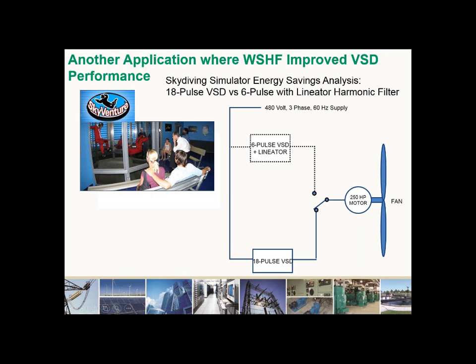These skydiving simulators are basically large fan systems blowing air out, and you step in and you can float on the air. You can see this is somebody sitting in a skydiving position. You can do various tricks and so on. A lot of fun to participate in. When they run these, they run them at varying speeds, but the two speeds they typically use are full speed, when the instructors or a very skilled skydiver is using the equipment, at 889 RPM fan speed, and the drive is going at the full 60 hertz.